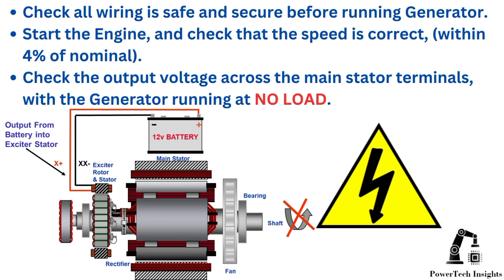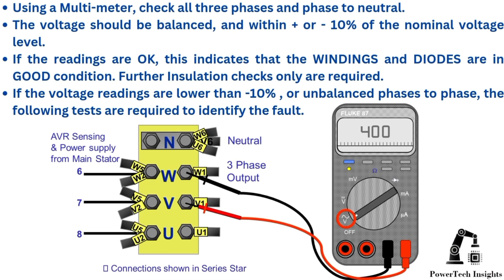Remove lockout tagout (LOTO). Start the engine and check that the speed is correct, within 4% of nominal. Check the output voltage across the main stator terminals with the generator running at no load. Using a multimeter, check all three phases and phase to neutral. The voltage should be balanced and within plus or minus 10% of the nominal voltage level. If the readings are okay, this indicates that the windings and diodes are in good condition — further insulation checks only are required.